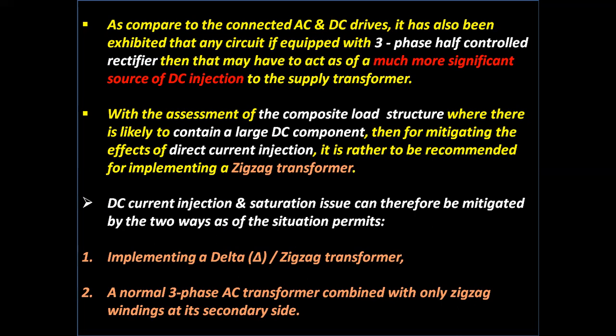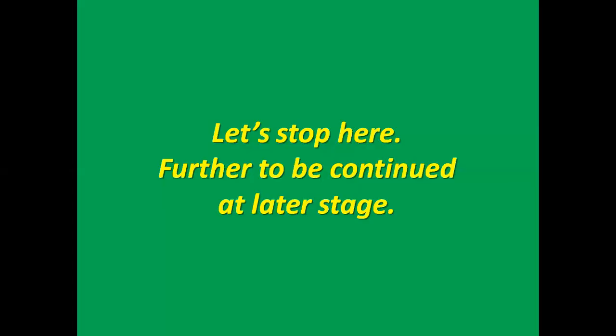DC current injection and saturation issues can be mitigated by two ways: number one, implementing a delta-zigzag transformer where the primary side is delta and the secondary side is zigzag; or number two, a normal three-phase AC transformer combined with only a zigzag winding at its secondary side. Let's stop here — further to be continued at a latter stage. Thank you for listening to the video.